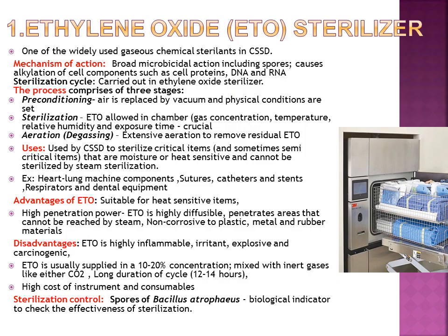The uses: used by CSSD to sterilize critical items, sometimes semi-critical items that are moisture or heat sensitive and cannot be sterilized by steam sterilization. So examples: heart-lung machine components, sutures, catheters, stents, respirators and dental equipment.